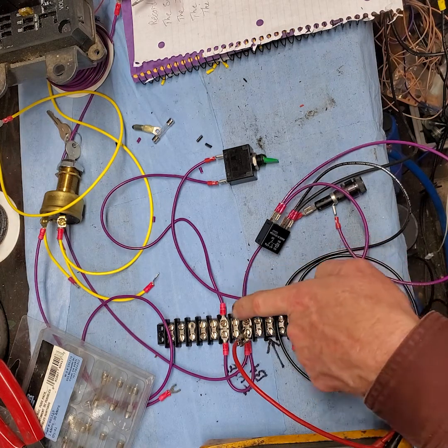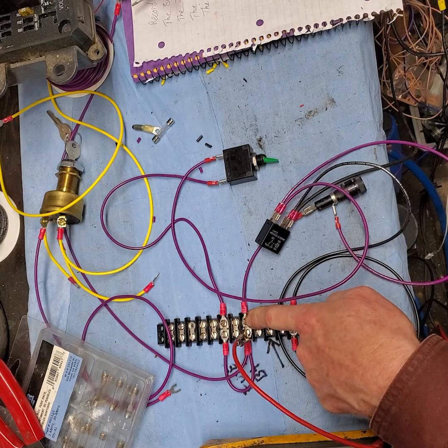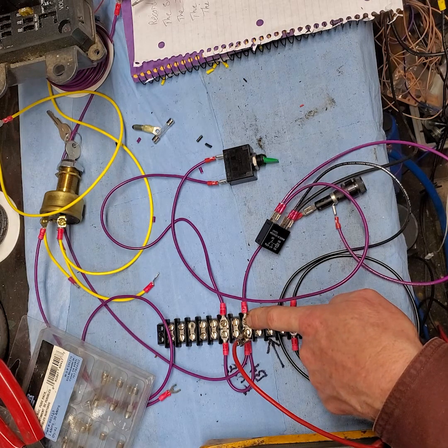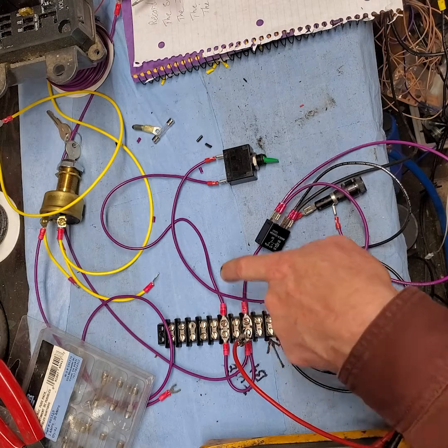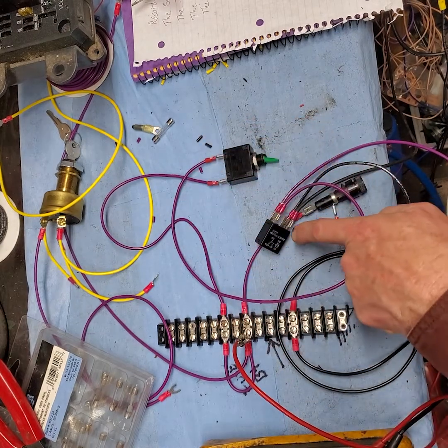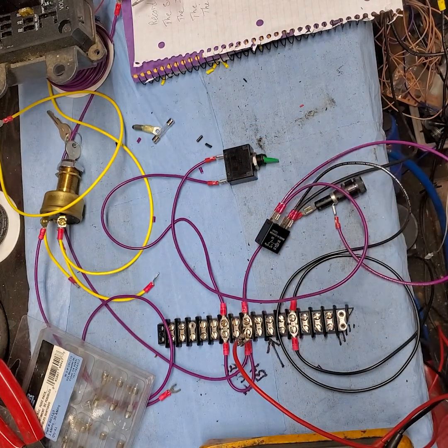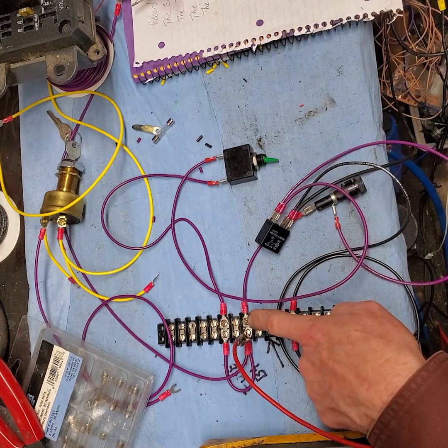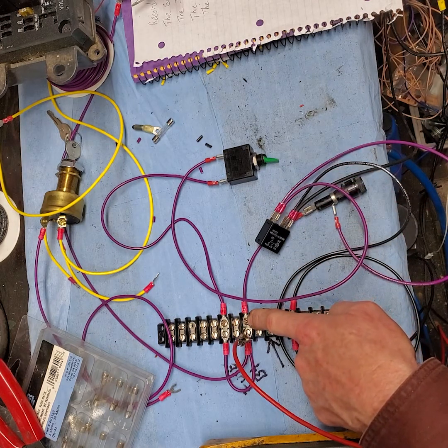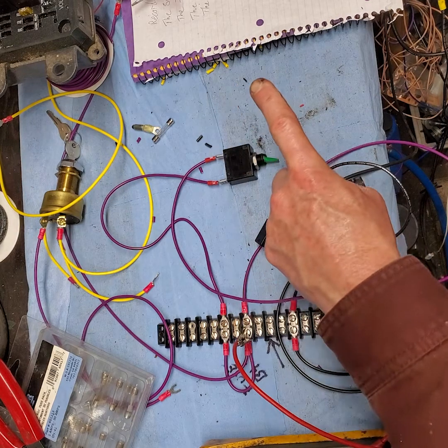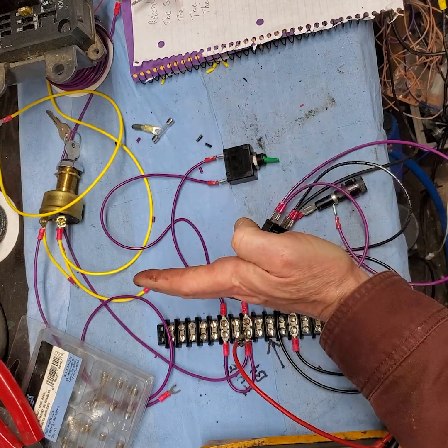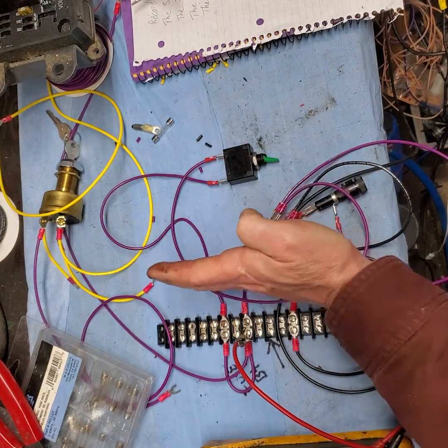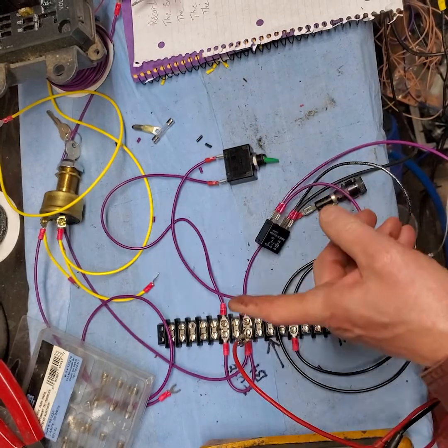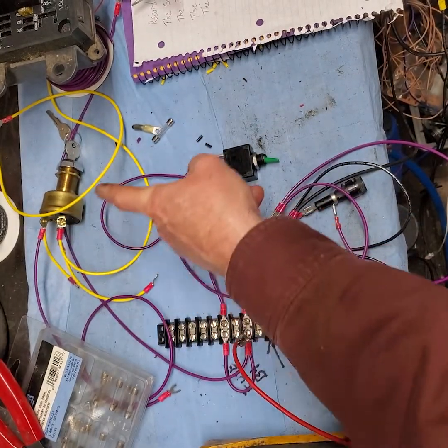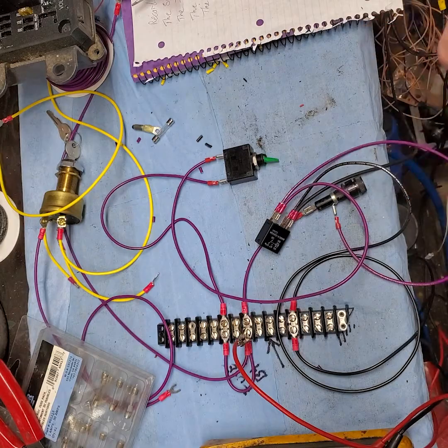So there's no power coming up to here. So that means the path is from this point over into my switch, out of my switch, into my relay, through my relay. The ground, that's a ground. So there is no power here. It's a ground. The power ends at the breaker. So if I open the circuit, I have power at that open circuit. And now I still have a path all the way through everything to ground.